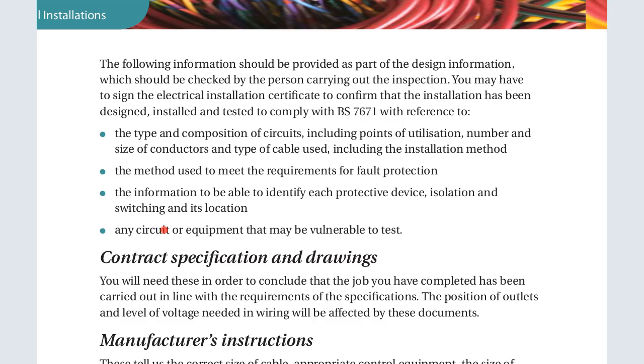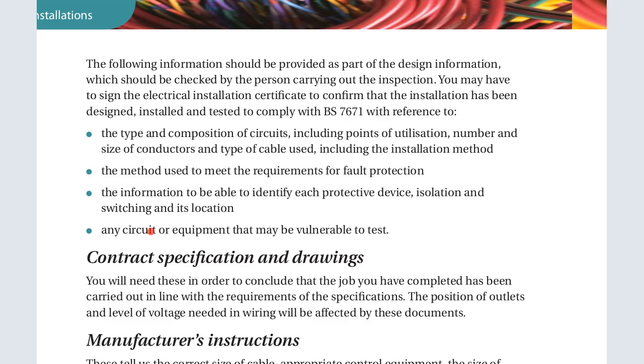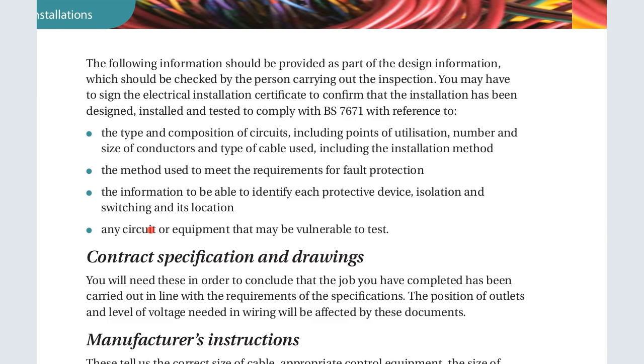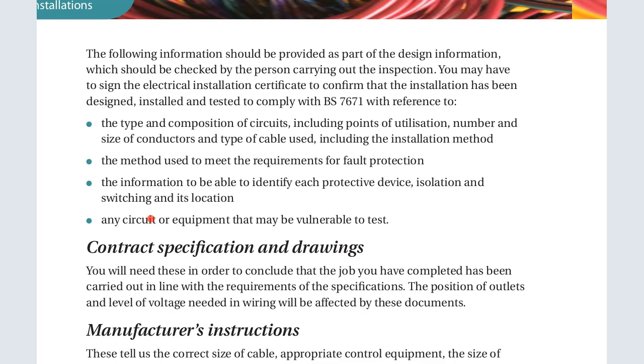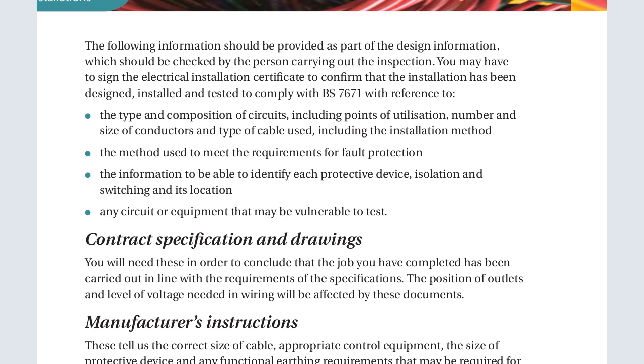The following should be provided as part of the design information, which should be checked by the persons carrying out the inspection. That is, they may have the signed electrical installation certificate and information. That is the type and composition of the circuit. We have the method used to meet the requirements. We have the information to be able to identify each protective device. We also have any circuit or equipment that may be vulnerable to the test.